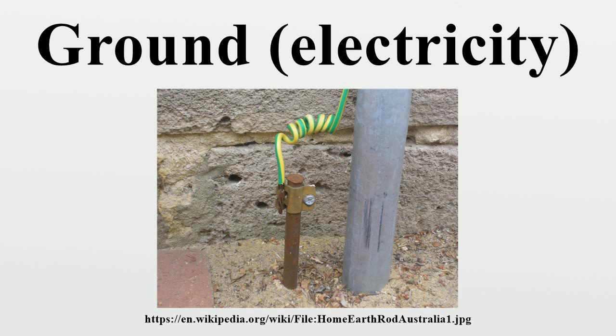This is due to the limited finite conductivity of the layers of soil in the earth. The gradient of the voltage may be so high that 2 points on the ground may be at significantly different potentials, creating a hazard to anyone standing on the ground in the area.